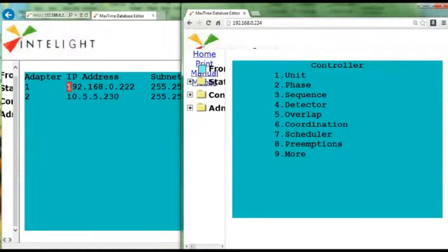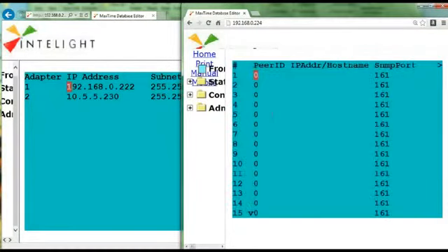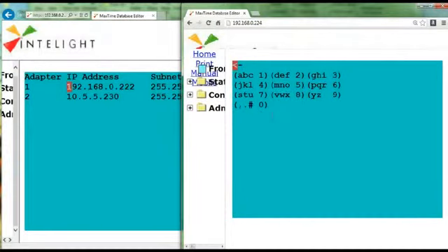The last step is to program the peer. We're calling for a peer, but we haven't defined the peer here. So to describe that parameter, we go to controller, number 2, 4 for peer, and we put in the peer ID, which is 222, and we simply put that IP address in. So the IP address was 192, as we can see over in the other screen, .168.0.222.